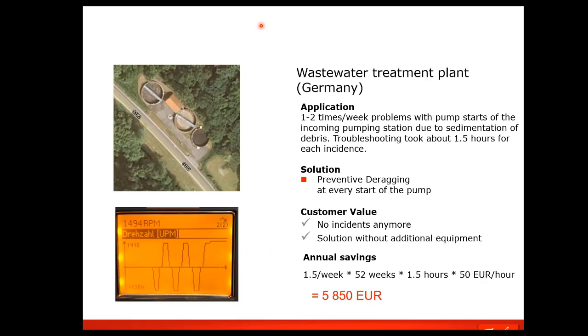Another site in Germany uses this, and they were also having the same kind of thing, 1 to 2 times a week. They would have problems with sediment and debris in the pump. So they were using the preventive function because sediment was just constant there. So every time it starts, they have it do a derag to clear itself and then run. And this is actually a scope feature in the drive, just showing speed and showing the deragging. So it runs backwards, then stops, runs forward, stops. And they did it 1, 2, 3 cycles, and then run to application.